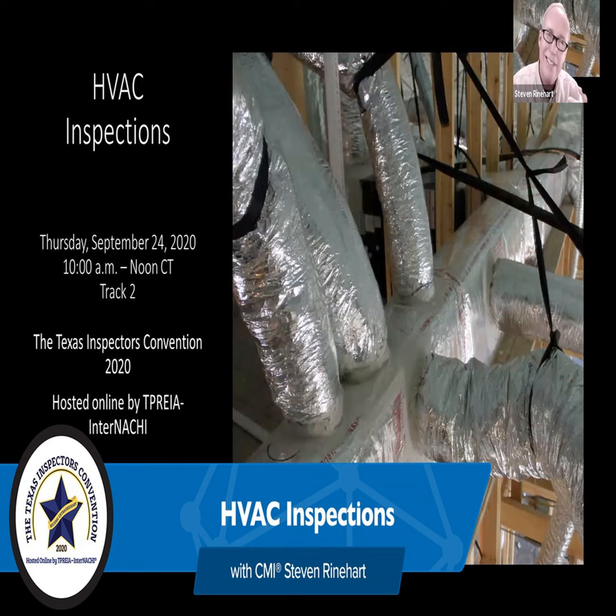It should go to a highly visible place to the occupant. You've seen them above windows, front patio. Now, when you drive up and go to the front door, you see that condensation from the secondary pan over the front door. And they've gone to Home Depot and got more pipe and extended it all the way down, and it's going in the front garden, and you see water running out of it, you know you've got a problem. The secondary is acting as the primary. Those are clues you get as you're walking around.